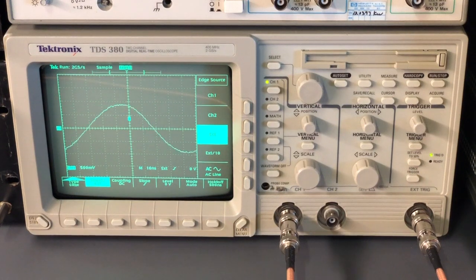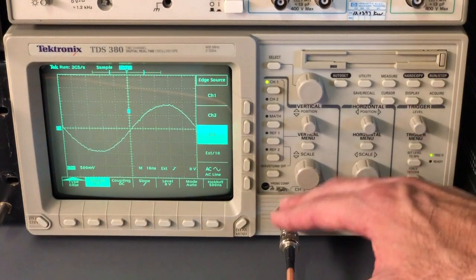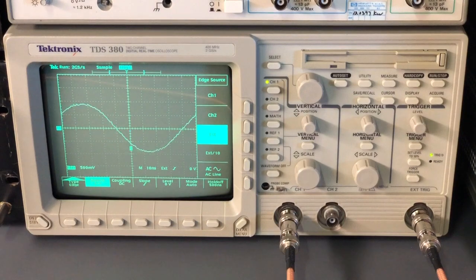That accuracy is a higher accuracy than the time base in the frequency counter, and it's a higher accuracy than the frequency counter could display. Always very important when you're making a calibration that your reference signal has more accuracy and is more stable than the signal that you're trying to calibrate.